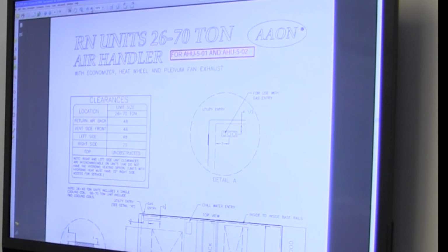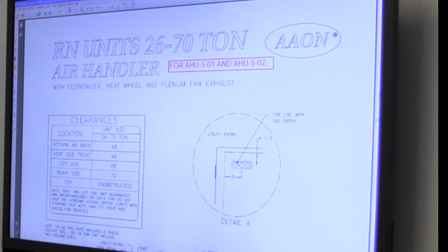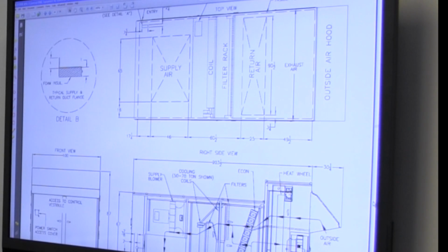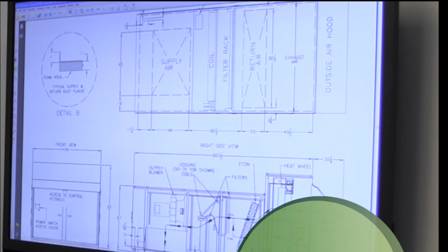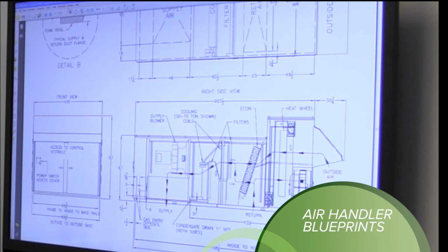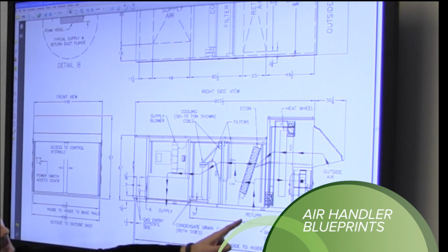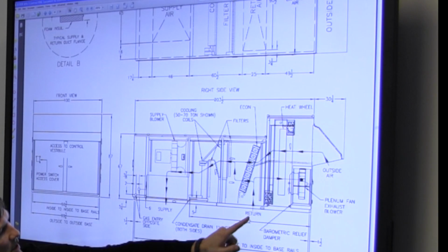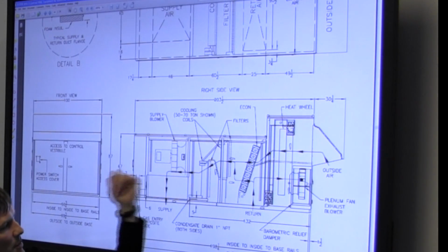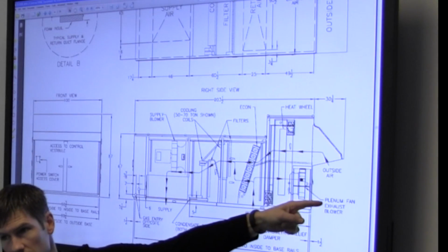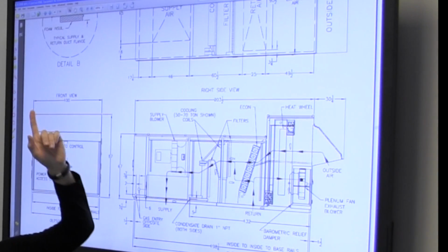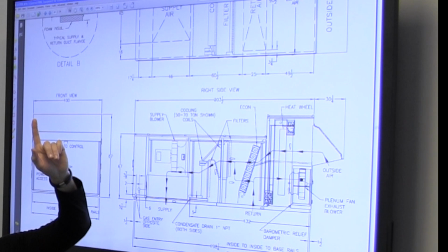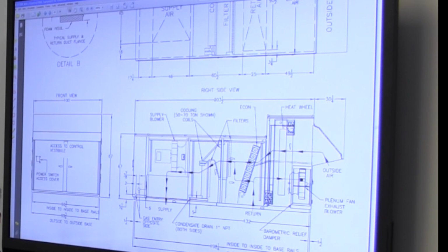Here is the cross section of the unit. I'm going to show you all the components here. Looking at the elevation, the side of the unit, starting at the beginning, your return air comes in from the building and it has a choice. It can either recirculate through these dampers and go back through the unit, or it can leave the building and go through the exhaust. The 3 units on this side, the 2 largest units are 100% outside air all the time. The smaller unit sometimes has recirculation. I'm not positive of how they're controlling that.